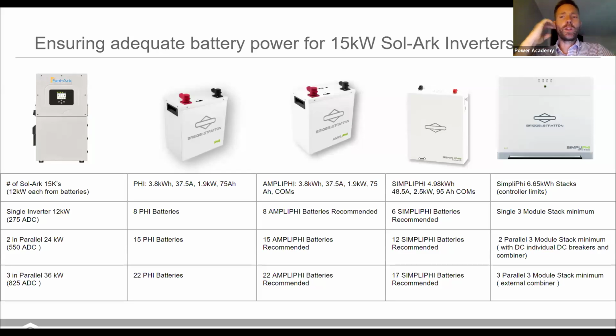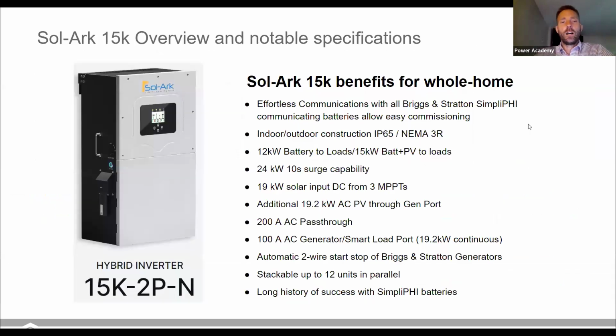Typically the SimpliPhi batteries have always had a C/2 rating. Our latest battery offering means that you can pull about half the power of a battery out per hour. So a C/2 rating would be half the power. If I've got a 10 kilowatt hour battery bank, I could pull out about 5 kilowatts typically. With our newer battery, we've got higher power output. But for a 15K, we'd need a minimum of 3 6.6 batteries, so a single 3-module stack, to run that properly.